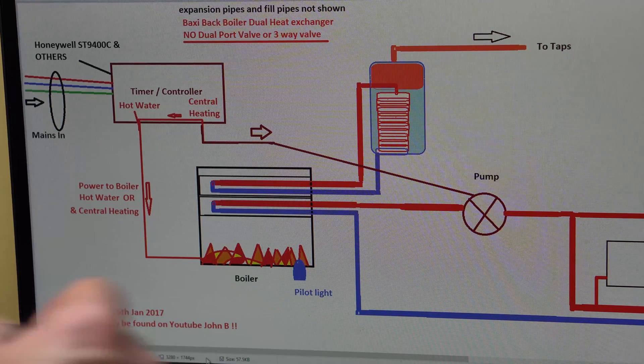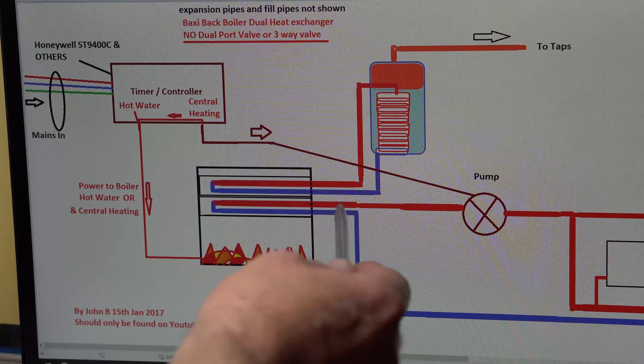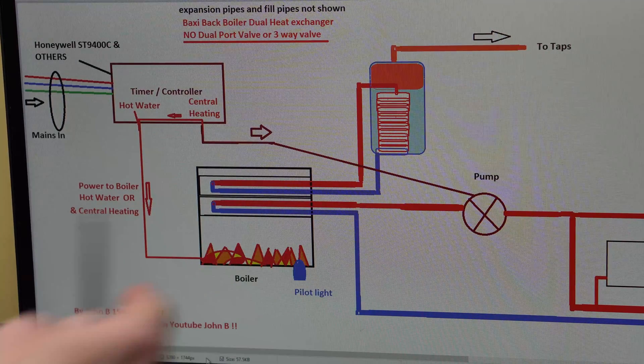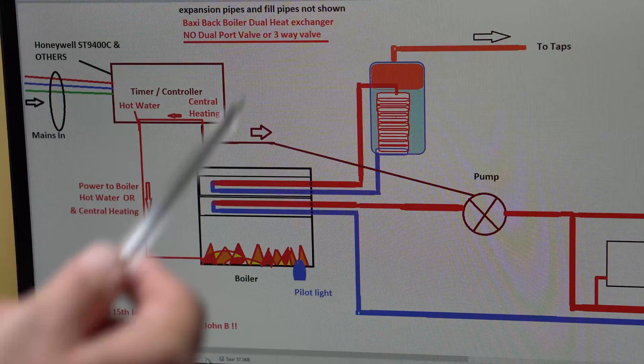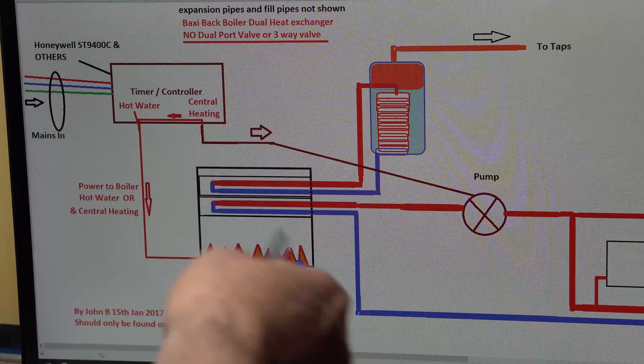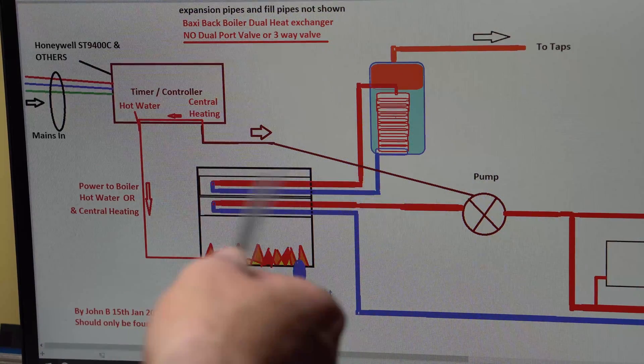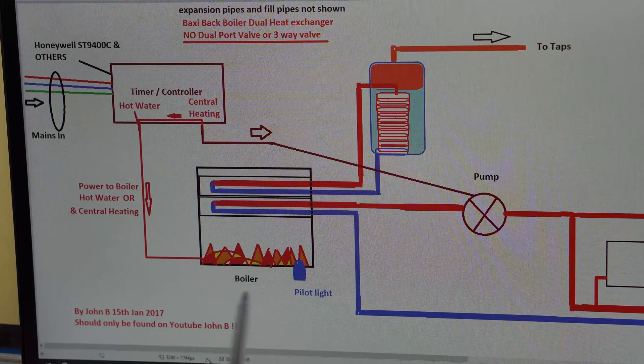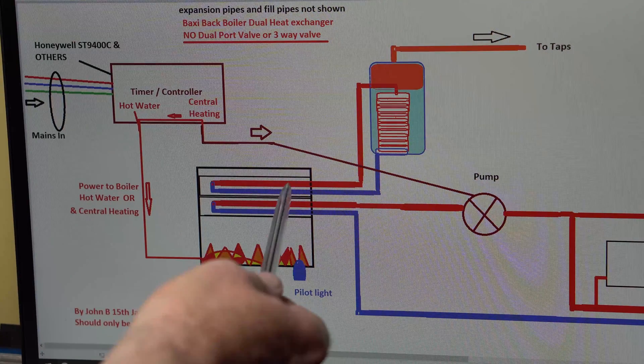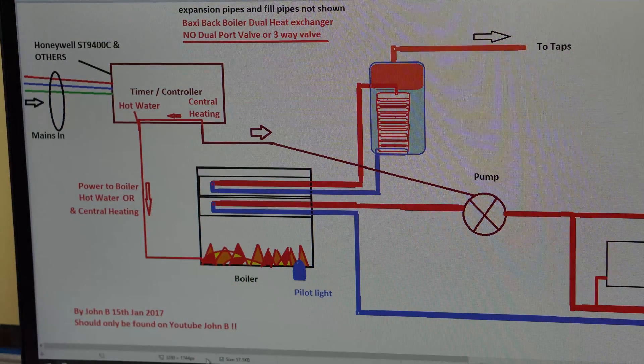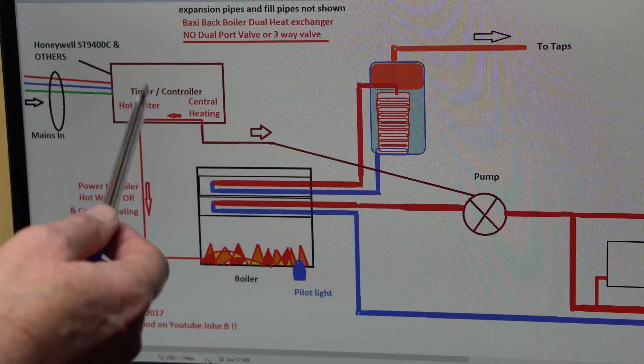As I say, if you've got a diverter valve, diverts the water to hot water or central heating, that's the first thing you check. The valve can get scaled up. It can also cause a boiler to bang. In this case, no diverter valves. It took me a while. I was looking through the gaps in the floorboards, looking for a valve, couldn't find one anywhere. And that's because this Baxi back boiler has a dual heat exchanger. One for the water, one for the central heating.